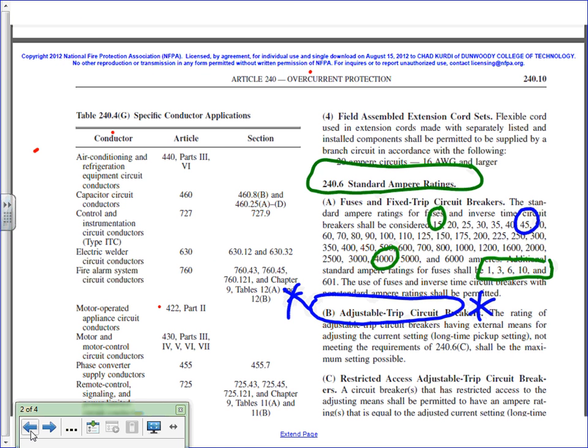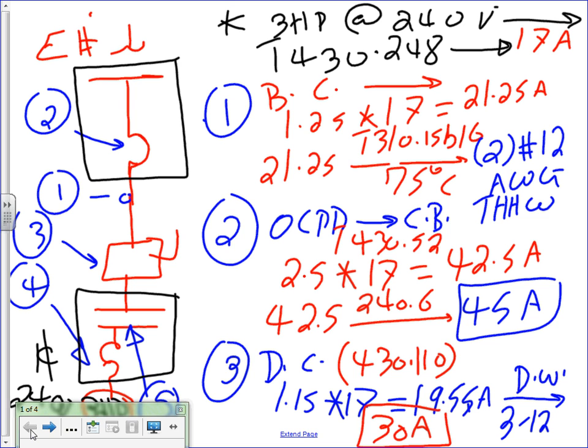Okay. So any questions? What we did: we installed a 45 amp circuit breaker. We pulled conductors, two conductors number 12, out of that, and we brought a disconnect. My disconnect was 30, and a controller. We didn't size the controller. It's just a NEMA. Later on, we'll size it. Overload protection was whatever the size is, and then all the conductors in between.